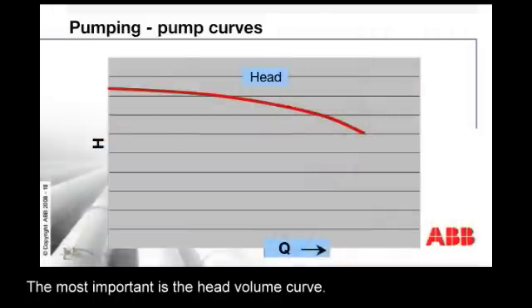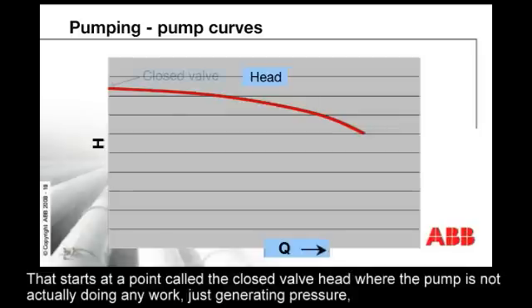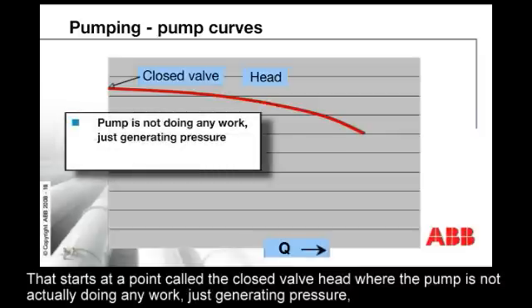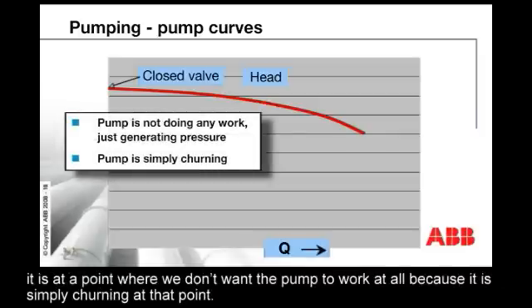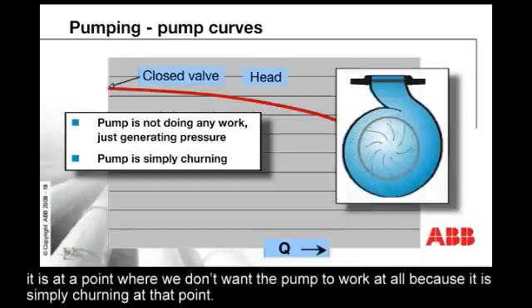The most important is the head volume curve. That starts at a point called the closed valve head where the pump is not actually doing any work, just generating pressure. It's a point where we don't want the pump to work at all because it's simply churning at that point.